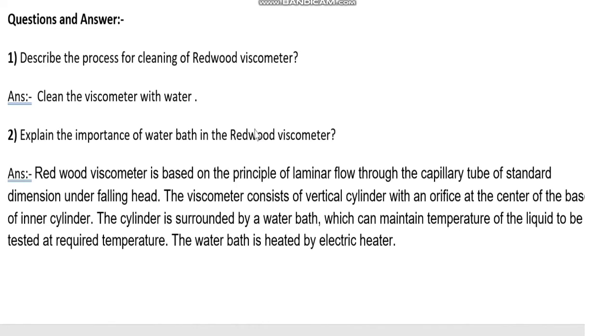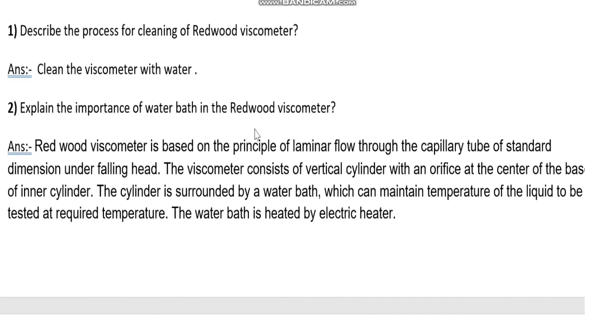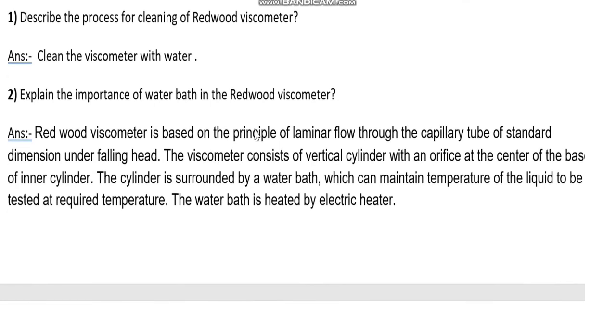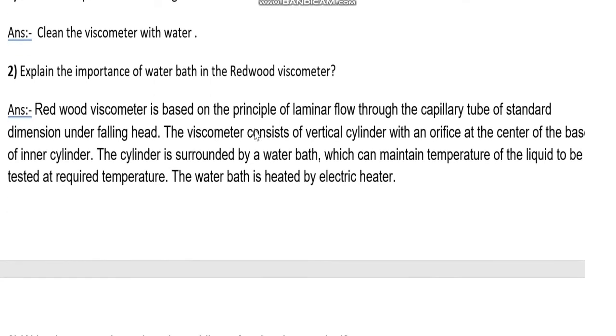The Redwood viscometer is cleaned with water. Regarding the importance of the water bath: the Redwood viscometer is based on the principle of laminar flow through a capillary tube of standard dimension under a falling head. The viscometer consists of a vertical cylinder with an orifice at the center of the base of the inner cylinder, surrounded by a water bath which can maintain the temperature of the liquid at the required temperature.